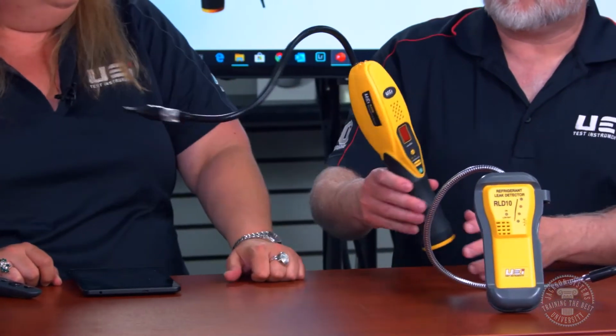So, now I hear there's something else out there. Do you have something? Yeah, Mark? Like I say, a couple of things to point out. One of the big differences between the two of these is the RLD15B has a pump. So it's actually drawing that sample in, across the sensor, rather than just relying on that ambient level. The other thing this does is it automatically calibrates. So let's say you've taken that coil cabinet front off, you've got saturation of the leak that's been in there. This is going to zero to that ambient level of gas, and then it takes a stronger concentration before it starts to go off again. So that kind of helps you narrow down where that leak is, because hey, it stopped. I move around, it starts to go off again. That means I've hit a higher concentration. Okay, so I'm closer to that leak source.